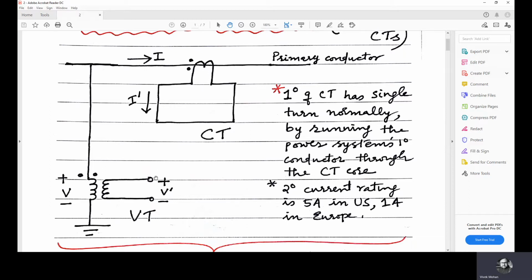So we assume the voltage sensing device to be connected to a VT secondary with infinite impedance, so that the entire VT secondary voltage is across the sensing device. But in practice, this is the ideal model. In practice, the secondary voltage divides across the high impedance sensing device and the voltage transformer series leakage impedance that we will see in the equivalent circuit.